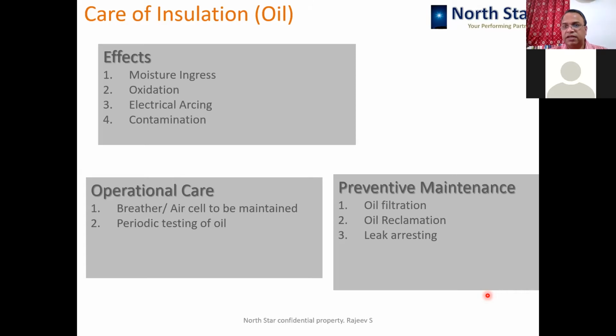Okay, so leaks are not to be ignored. Those are to be arrested very effectively. Okay, and leak arresting itself is a big job because you have to do a lot of jugglery and activities. The bigger the transformer, the bigger is the problem. So it is not to be ignored. And at the primary stages of the leak starting, you should do some preventive maintenance activities so that it is not further enlarged.